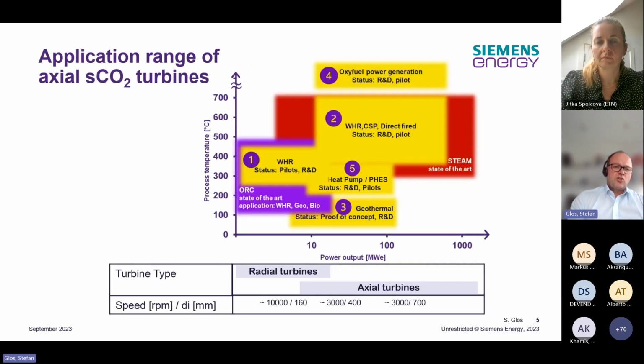Looking at the application range of the sCO2 cycles, here you see a chart which we have shown already a few times. You see the process temperature over the power output, and very roughly the areas of applications, and most of these were already mentioned by Alberto in his first presentation. One is the waste heat recovery application. In two, we have solar thermal or direct fired applications. Then in three, a special use case which we have been following for a few years, a direct geothermal use case. Number 4 is the oxy-fuel combustion, and 5 the area of heat pumps or pumped heat energy storage systems.